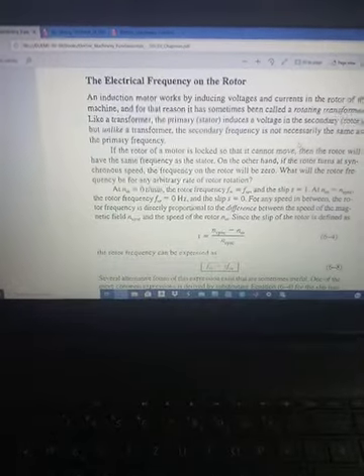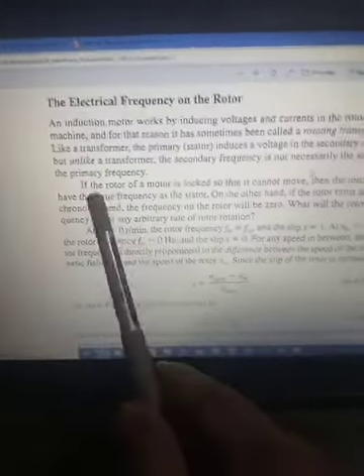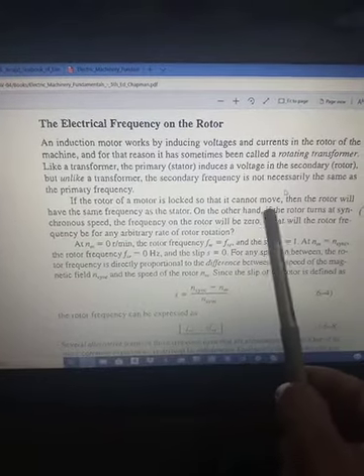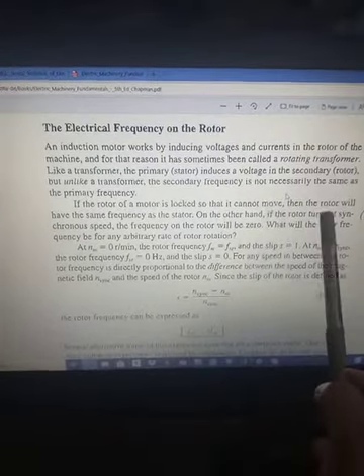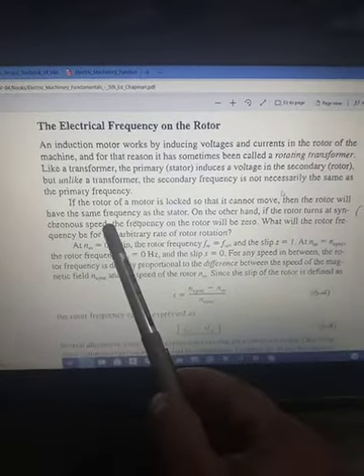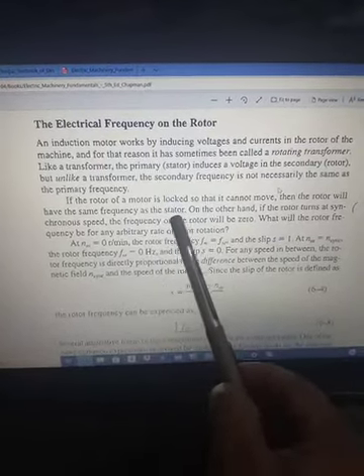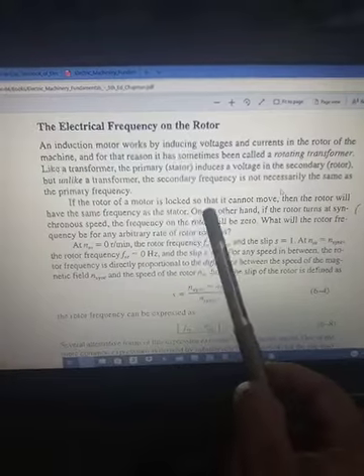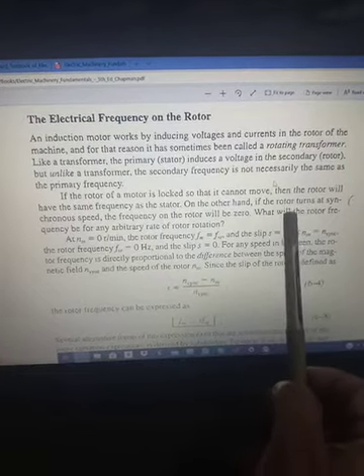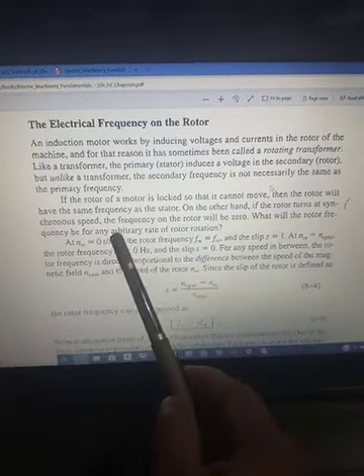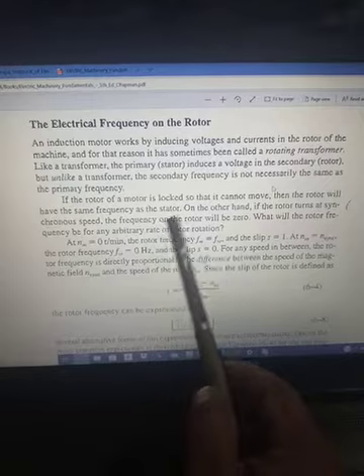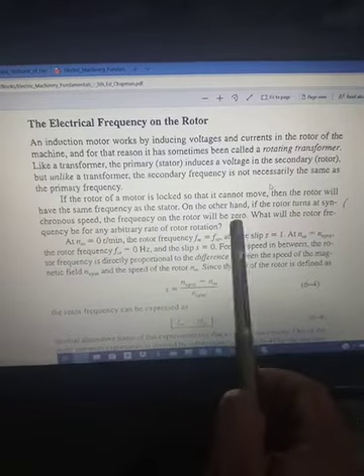If the rotor of a motor is locked so that it cannot move, then the rotor will have the same frequency as the stator. On the other hand, if the rotor turns at synchronous speed, the frequency on the rotor will be zero.